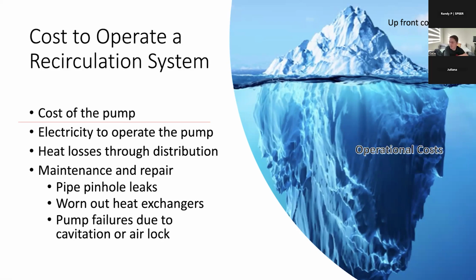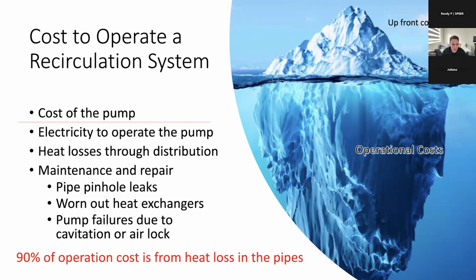And I wish I had some way to take a poll right now, but I'll go ahead and give the big reveal. 90% of the cost to operate a hot water recirculation system is from the heat loss in the pipes. So when we talk about the energy consumption of a hot water recirculation system, only about 10% of that energy is from the pump itself. Okay, so you can have the most efficient ECM motor pump, but if you're running that pump all the time, you're putting hot water into your pipes and you've got water returning back to your water heater, and your water heater has to keep cycling on to make up for those distribution losses. So it's really coming from the water heater, and the runtime of the pump causes the water heater to operate more frequently.